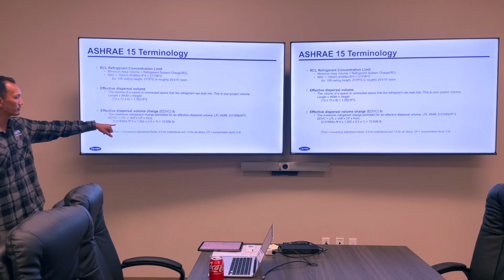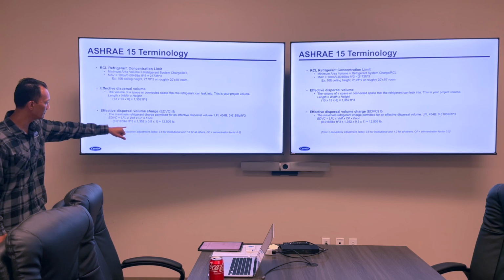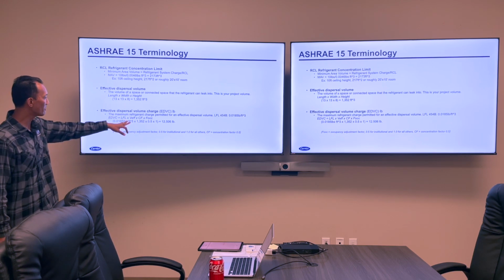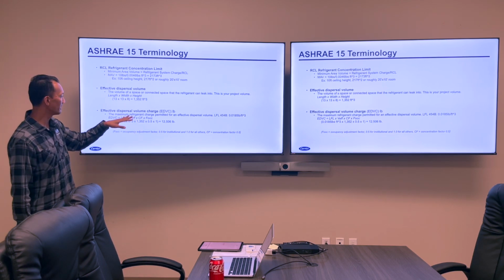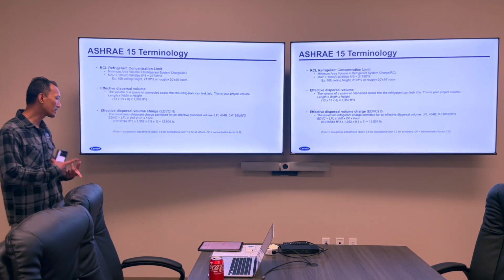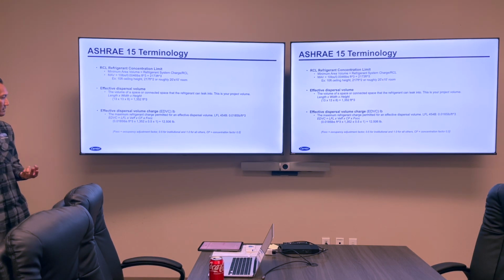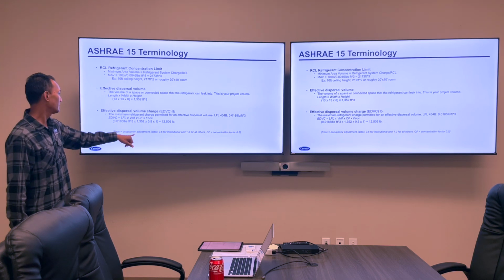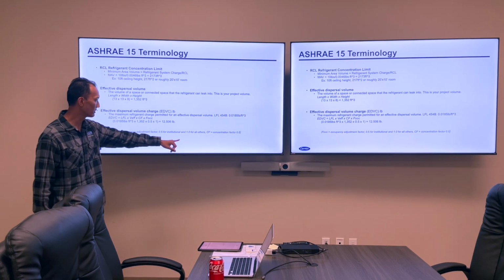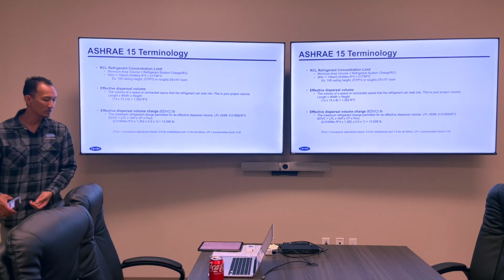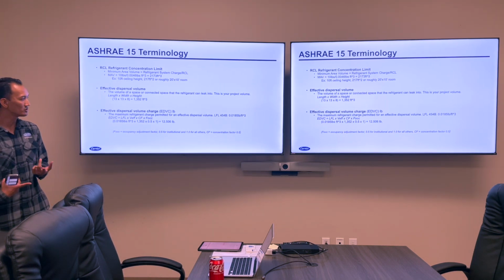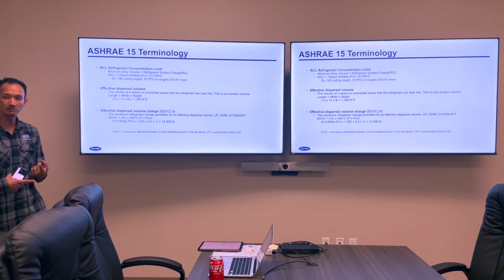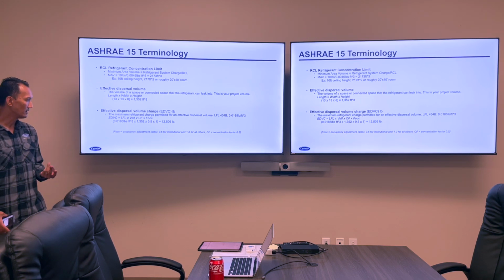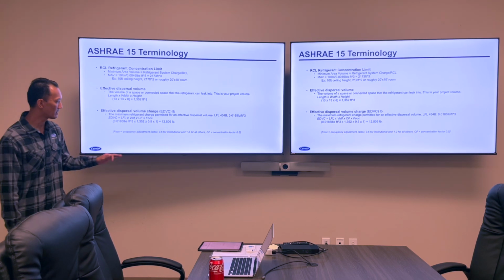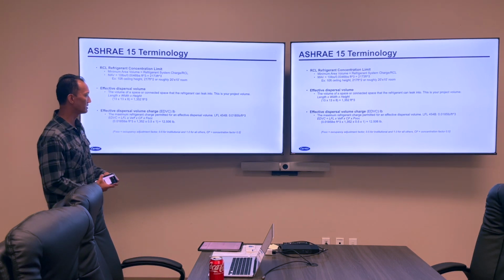For 454B, it's 0.0185 pounds per cubic foot. And then you multiply that by your effective volume, and then you multiply that by two constants, your occupancy factor and your concentration factor. For occupancy, it's going to be 1, and then for concentration factor, it's going to be 0.5 for institutional, so hospitals or assisted living, anything that's 24/7 operation, and then it's going to be 1 for everything else.